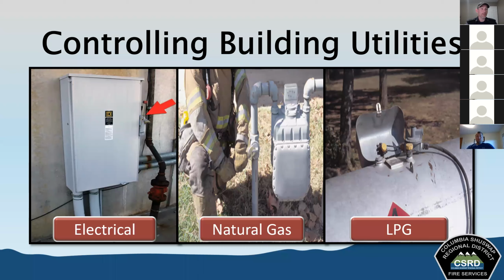What that means is it's going to sink to the lowest point possible, and it's going to pool in low areas. We may end up standing in pools of this invisible gas and be unaware of it. And if it mixes with air in the right quantities and gets an ignition source, it could be a really bad day for us. It's explosive in concentrations between 1.5 and 10%. So again, it's a fairly large range, almost 10%.